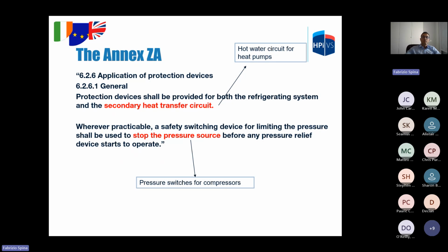Application of protection devices. Protection devices shall be provided for both the refrigeration system and the secondary heat transfer circuit. So when manufacturing heat pumps, the hot water circuit must be provided with protection devices. Wherever practicable, a safety switching device for limiting the pressure shall be used to stop the pressure source. This is typically the pressure switches for compressors.